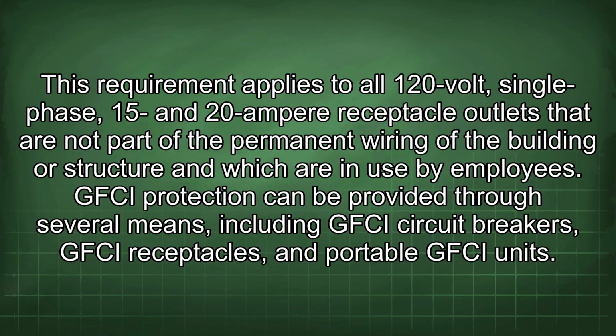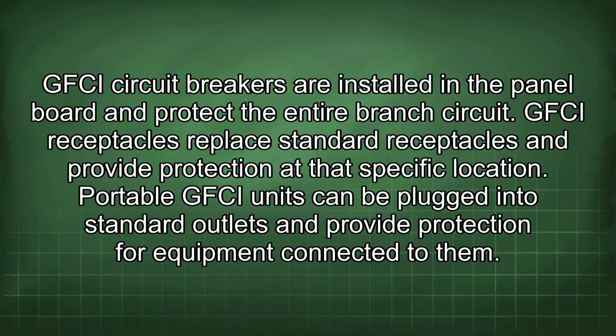GFCI protection can be provided through several means, including GFCI circuit breakers, GFCI receptacles, and portable GFCI units. GFCI circuit breakers are installed in the panel board and protect the entire branch circuit. GFCI receptacles replace standard receptacles and provide protection at that specific location. Portable GFCI units can be plugged into standard outlets and provide protection for equipment connected to them.